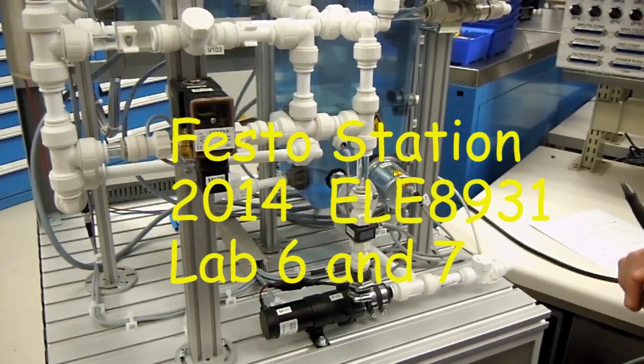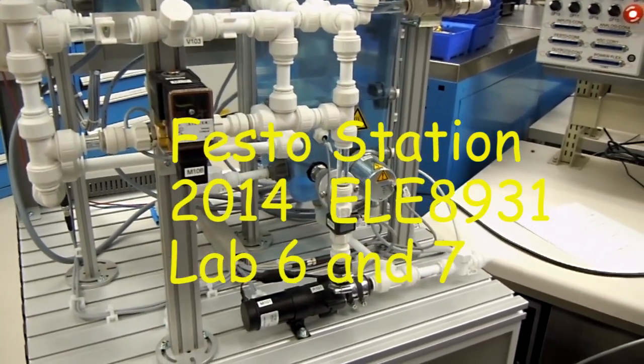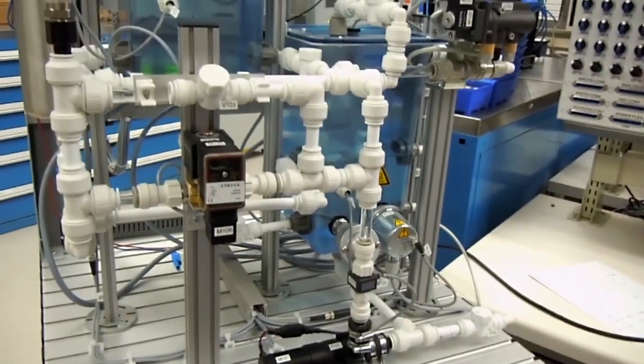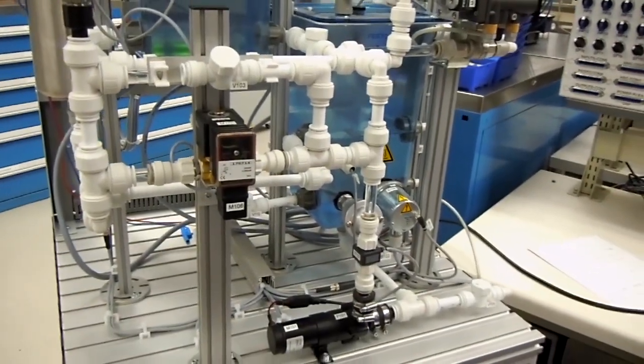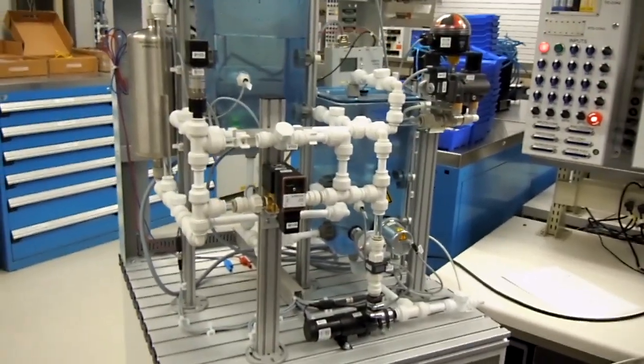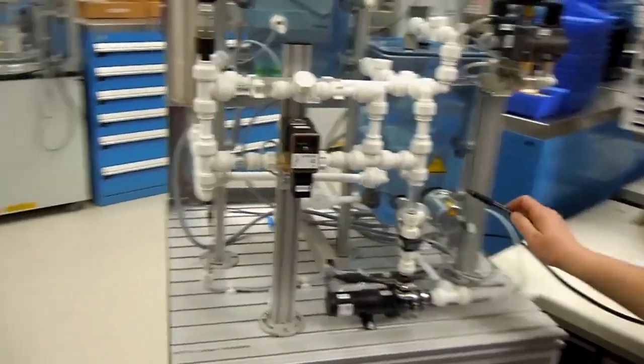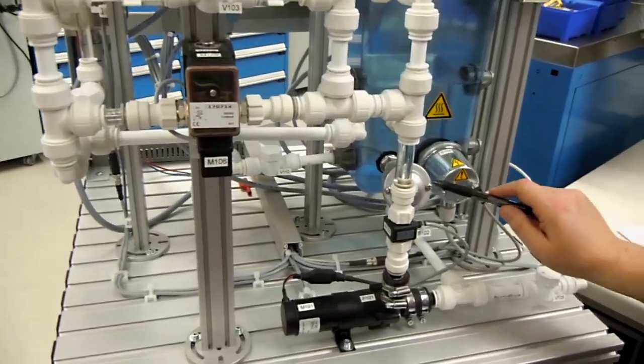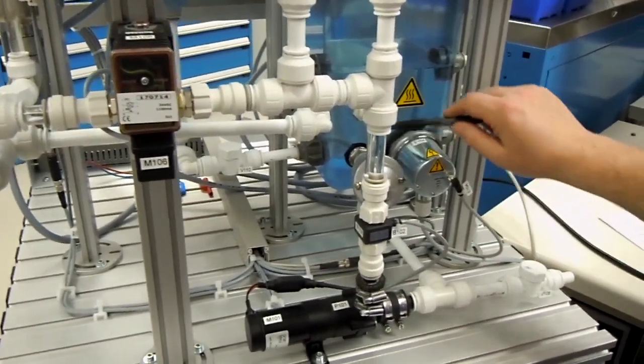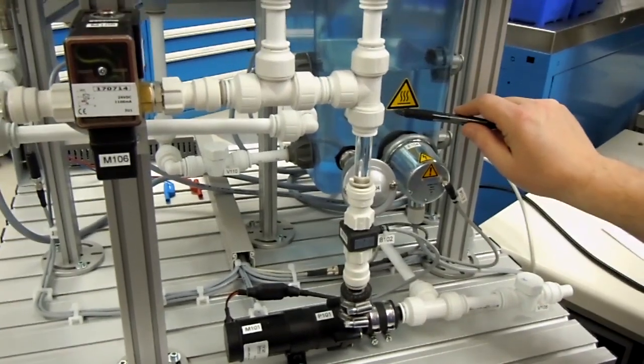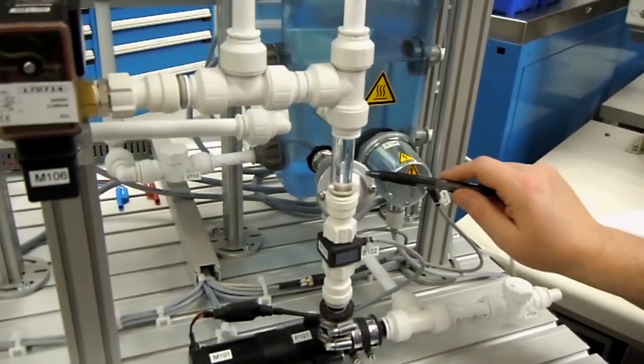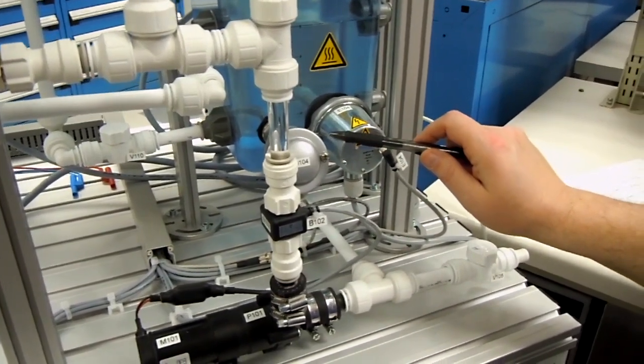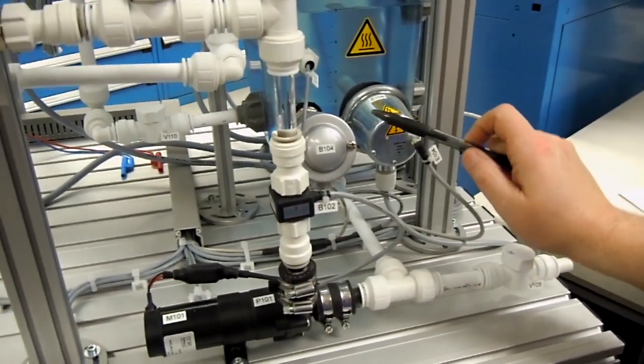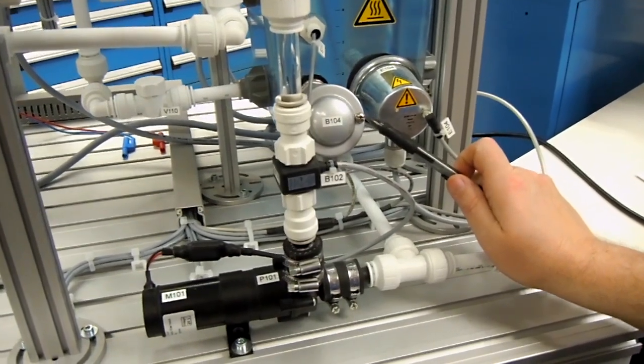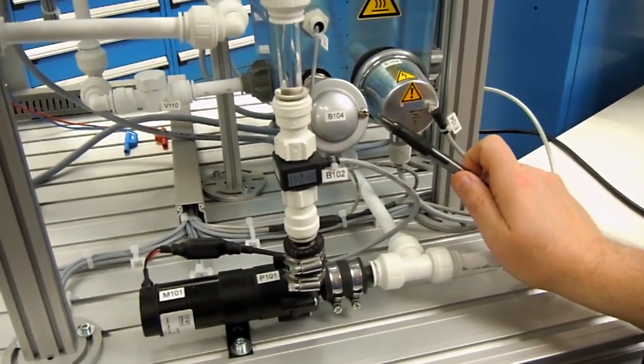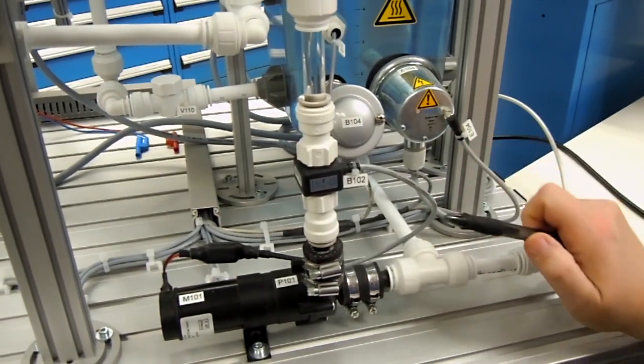Alright, this is the Festo Station that we'll be using in lab number 6 and lab number 7. To begin with, I'm going to look at the 4 analog sensors that measure various signals like temperature, pressure, level, flow. To start with, this here is the RTD temperature sensor. It has a rod that goes into the tank to measure the tank temperature. And it's an RTD, so there are 3 wires attached to it. It measures a range of 0 to 100 degrees Celsius, and its resistance changes by 100 to 138.5 ohms in that temperature range. So that's for measuring temperature.